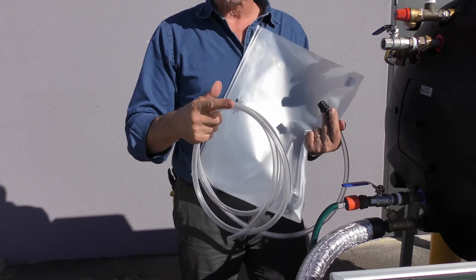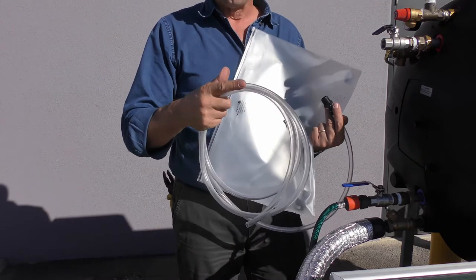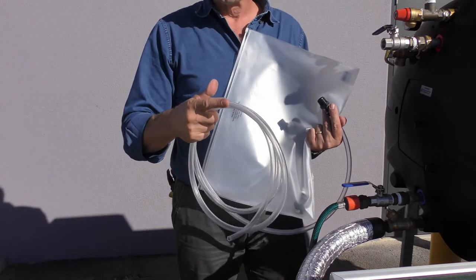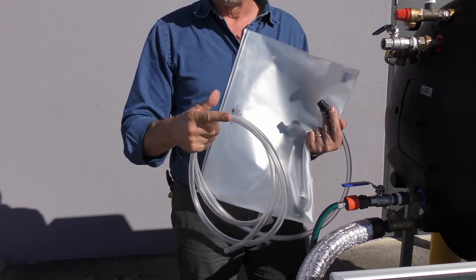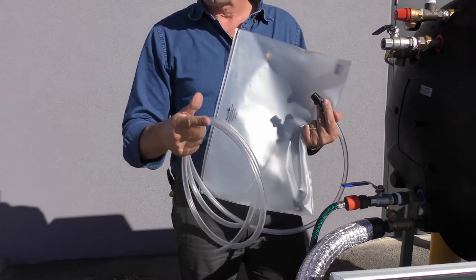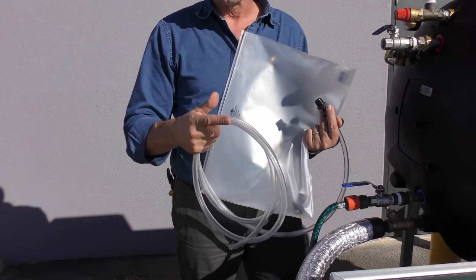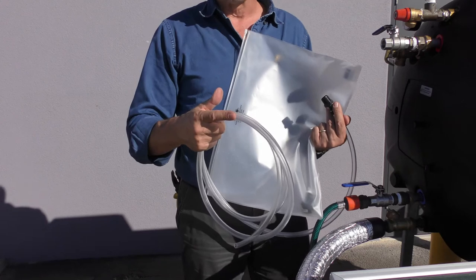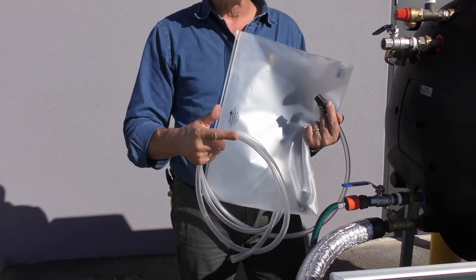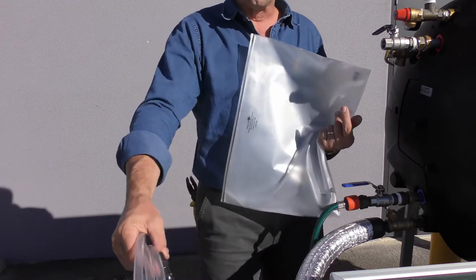The full five litres must be installed at every location around Australia with this system. Outside of Australia, in countries where temperate climates can drop well below zero for a long period of time — like South Korea, Europe — we recommend two bottles of the heat transfer fluid. Here in Australia, you can get away in most locations with one, though at the top of Mount Kosciuszko I'd recommend two bottles.